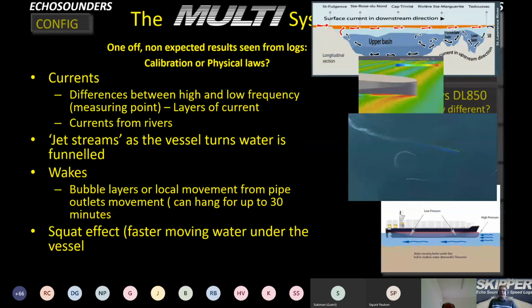And what you often find, or sometimes find, is that the current is actually going in a different direction under the water than it is on the surface, because on the surface it's being blown by the air, by the wind. And if you're near a river, it might be fresh water at the surface and the salt water is tidal underneath going in a different direction. So that is something you have to be aware of if you're trying to calibrate in that kind of area, or if the customer says that it's all wrong when they're in a river. It might actually be right, but they don't see it on the surface.